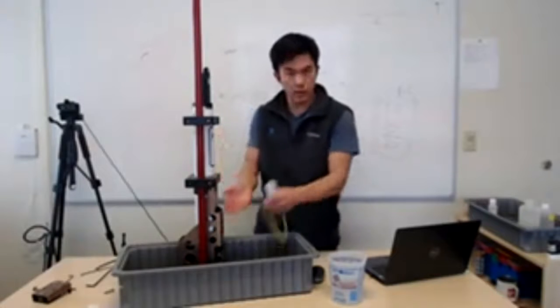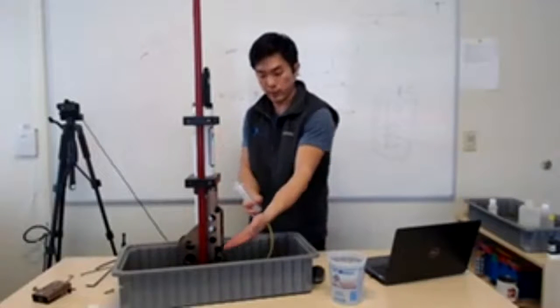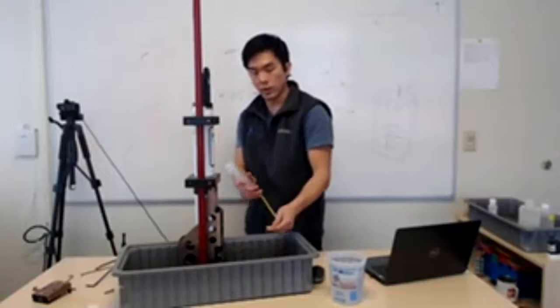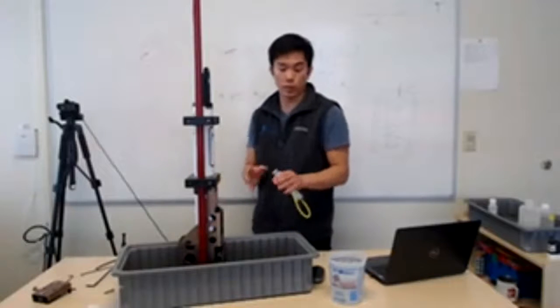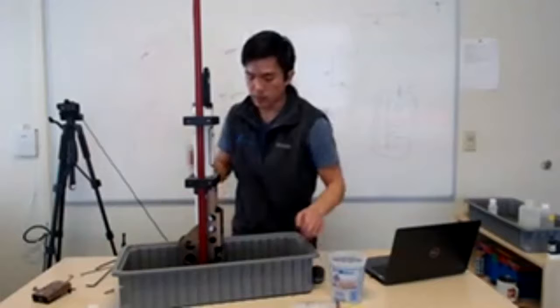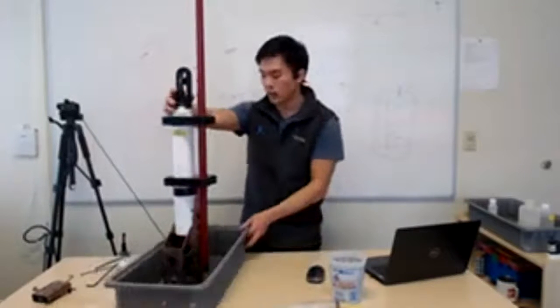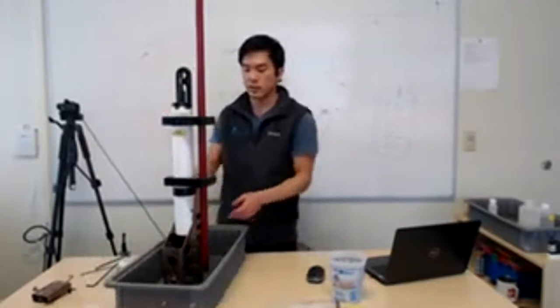Okay, so I've poured the seawater out of the flow path. I've flushed the pH sensor area with deionized water. Now I'm safe to remove it. Any water on the connectors will be clean DI water, much less likely to damage the sensor.